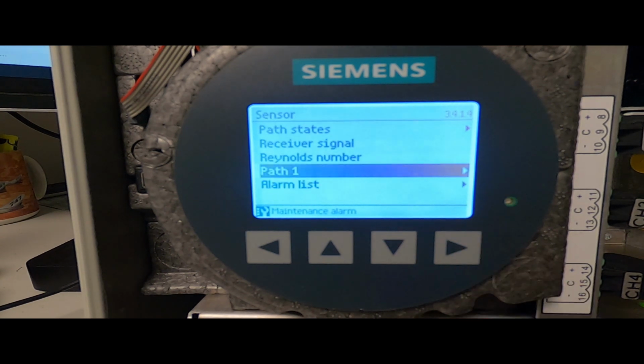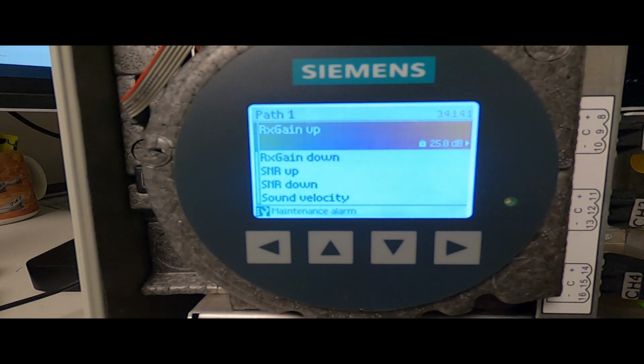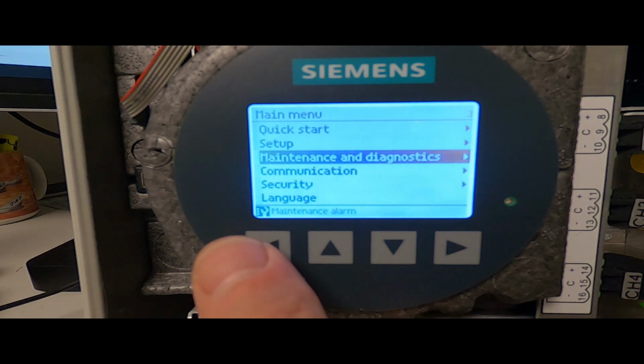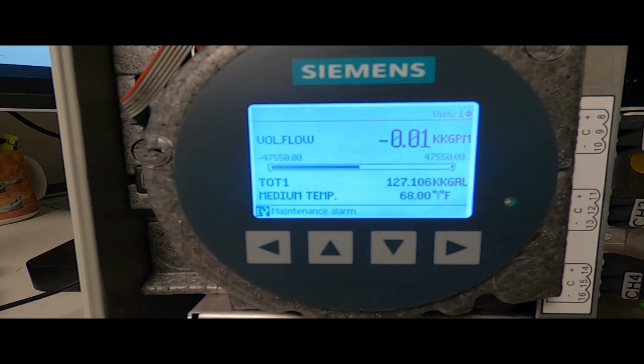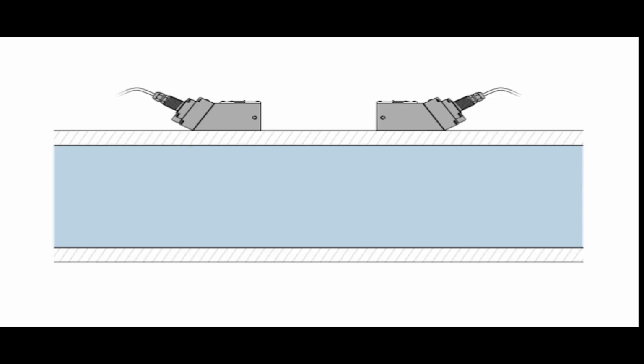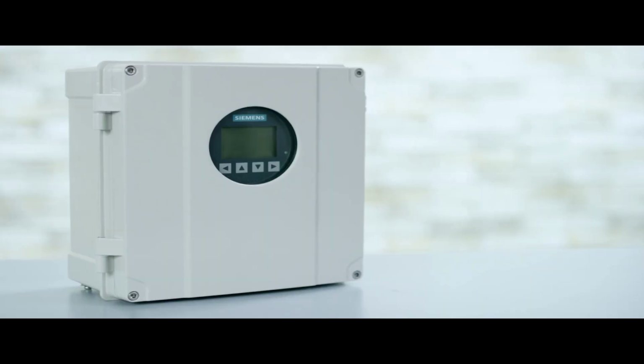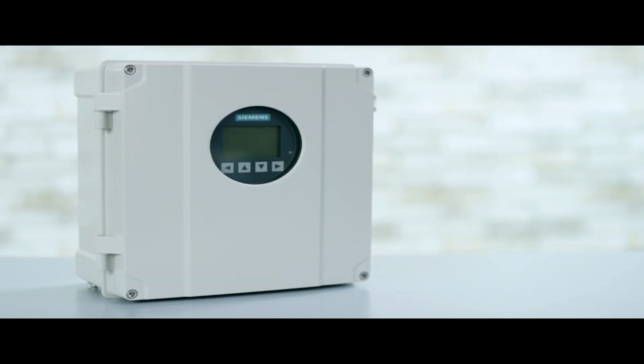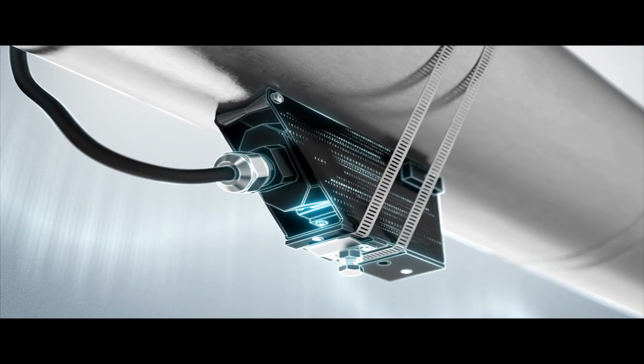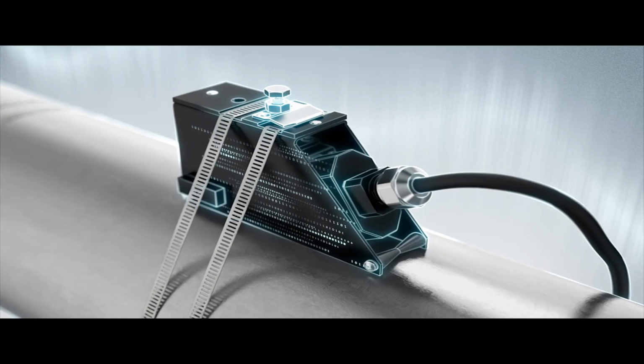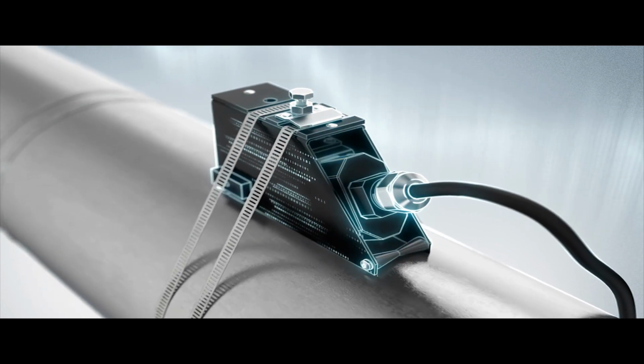The meter should exhibit proper diagnostic values for signal strength, and you should have a flow measurement which will be at or very close to 0. Achieving these results confirms your flow meter is 100% functional, since it is operating exactly as it would in a normal application, transmitting and receiving a sonic signal. You have verified the functionality of the electronics and also the sensors, the sensor coupling to the pipe, and the sensor cables.